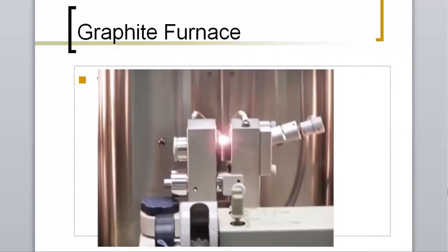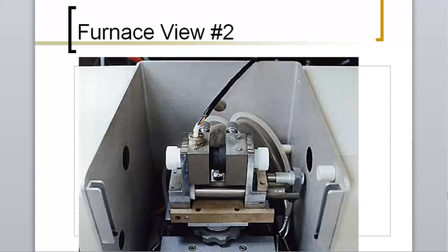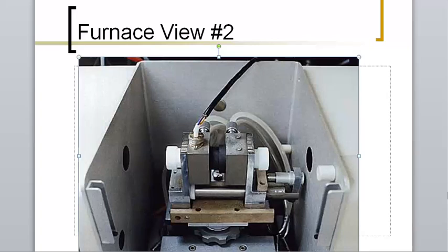Here's a real picture of the internals of a graphite furnace. It looks a little different than maybe what you would expect or what you would envision with the atomic absorption, but it's not because you were wrong in thinking what it would look like. It's because this is really kind of a bad picture. So I can give you a better picture of a graphite furnace and it looks something like this. So this is very similar to the AA that we have now. A lamp goes out one end and it goes into the detector on the other end, and here instead of the burner head, this is where you would see the graphite furnace piece itself, and that's what you're seeing here in the middle of the block. Here in the center you almost see the graphite tube that's on the inside of there that heats it up and kind of closes off your sample from the outside.